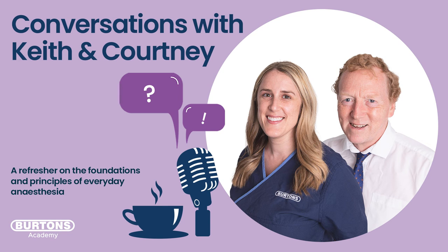What are we going to get from the oscillometric reading? We'll probably get four things: a heart rate during the measurement period, and then the three values we're really looking for — systolic, mean, and diastolic pressure. Now, this is a bold statement: oscillometric devices don't measure anything per se. They infer a value from what they do measure. There's a subtle difference — the oscillometric system looks at pulse waves, makes regression lines on the slopes going up and down, gets the intersect, and then determines that the intersect is some factor of the mean arterial pressure.